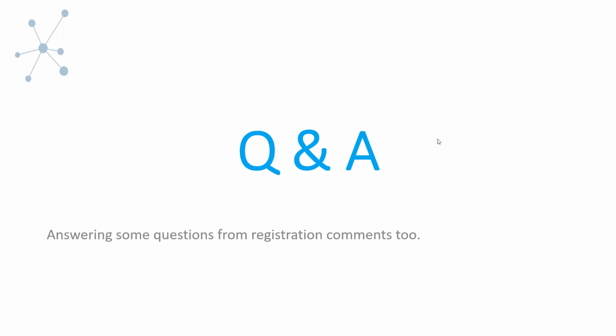And then there's a question about our channels. Are they disposable? The answer is no. The channels are designed to be used repeatedly, and generally, when customers purchase them, we will talk to you and try to guide you in coming up with the best cleaning protocol for the type of samples that you have. So they're meant to be used again, not disposable, and you can definitely clean them. We're happy to work with you and share our experience that we've had internally and with our other customers to help you develop a cleaning protocol to make sure everything is okay.